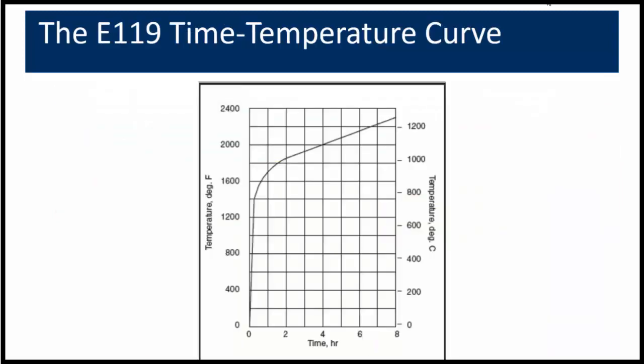At best, the test can be considered a relative index system to compare designs. It does not predict actual performance — hourly ratings are not what the real survival of the components will be under all conditions. This next slide is an illustration of the ASTM E119 standard time temperature curve. The furnace must achieve prescribed data points: 1,000 degrees at five minutes, 1,300 degrees at 10 minutes, 1,550 degrees at 30 minutes, 1,700 at one hour, 1,850 at two hours, 2,000 at four hours, and 2,300 degrees at eight hours or more.